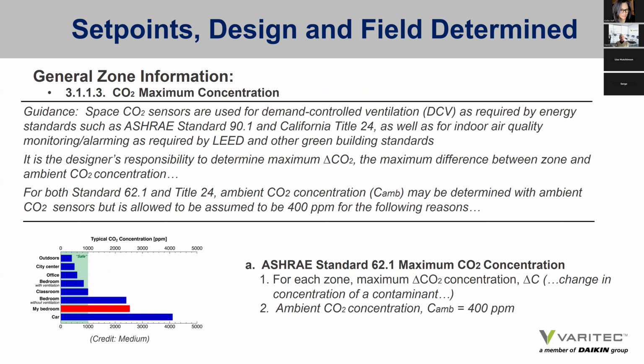The general zone information also includes CO2 maximum concentrations. It says space CO2 sensors are used for demand control ventilation as required by the energy standards, such as Standard 90.1, California Title 24, as well as for LEED. It then goes on to say that it is the designer's responsibility to determine the maximum CO2 differential between the zone and the ambient outdoor air condition, which Guideline 36 specifies to be a common value of 400 parts per million.